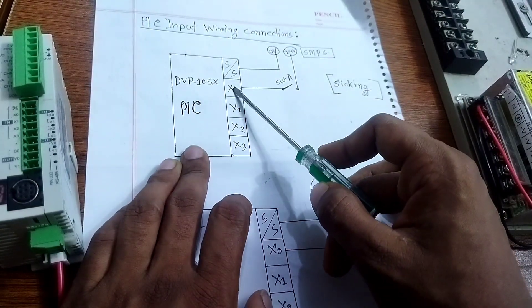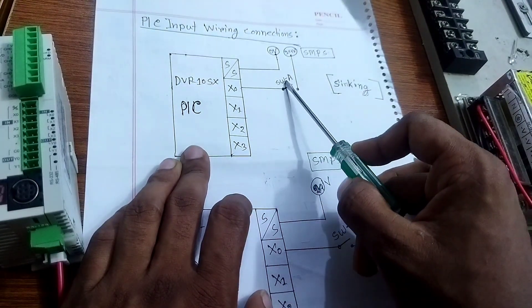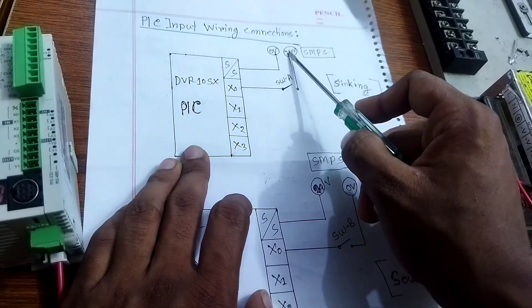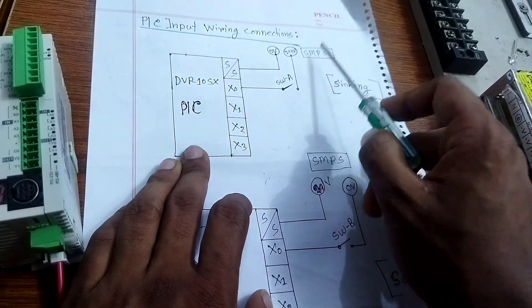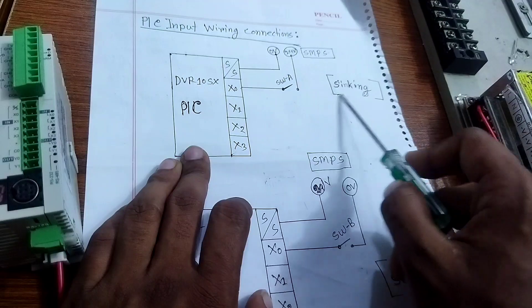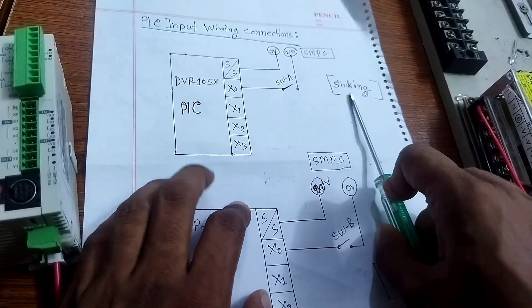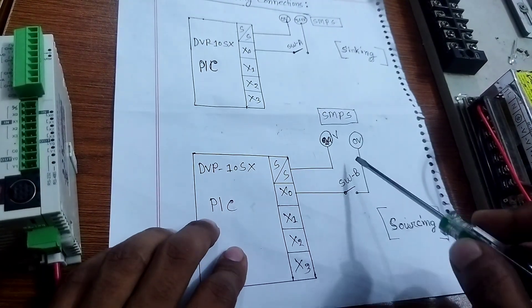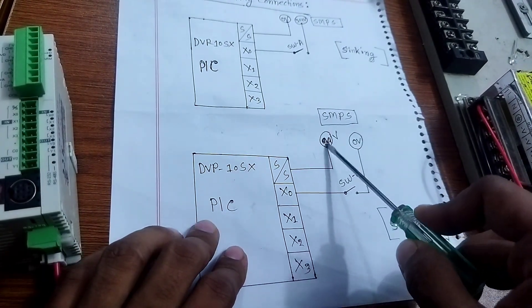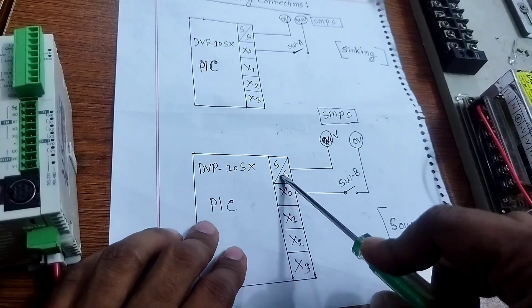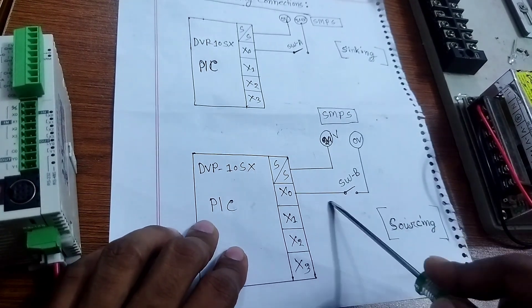This is sinking wiring for this PLC. In the next diagram, SMPS 24 volt connects to SS port, then X0 connects to switch B and zero volt to the SMPS. This PLC wiring is sourcing, or source wiring.